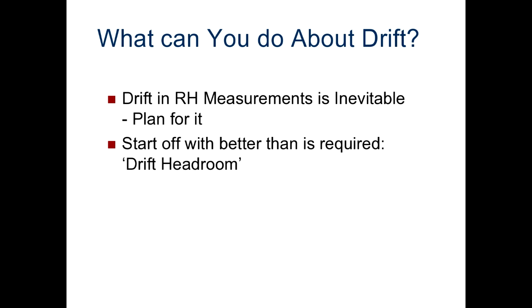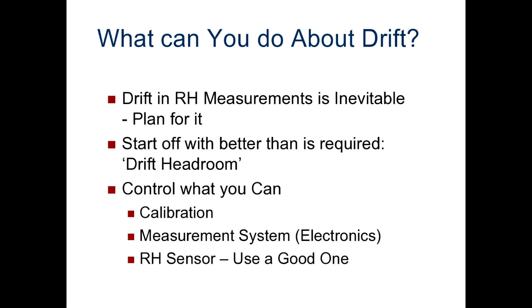It's also important to control what you can. And that means getting the best calibration that you can, ensuring that the entire measurement system, including the electronics, are of the best quality that you can get. And the RH sensor that you have is the best one that's available for that application, because they are not all created equal. And it's important to look at prevention.